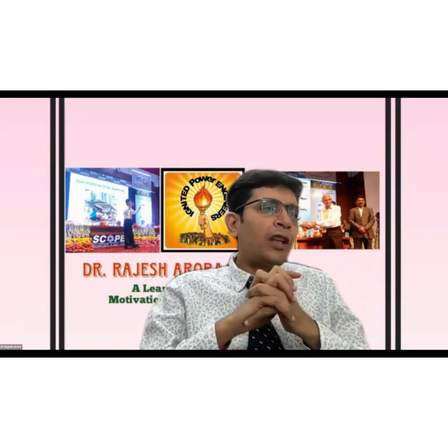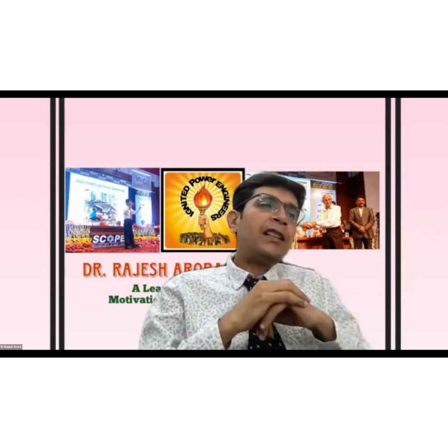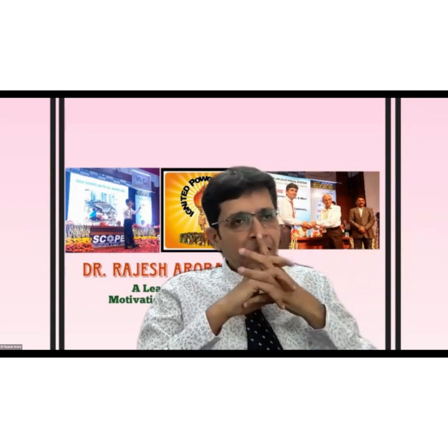Now coming to online TODOS, transformer oil dry out systems. Their specification has already been given in the CEA standard specification technical parameters. Apart from that, read IEEE C57.91 and IEC 60076 part 7, which talk about loading guides for transformers. Another good document is CIGRE 349, in which they classify the transformer based on relative saturation as good, fair, probably wet or wet. CEA has given the specification of the online dry system in Annexure U, which you can refer to.